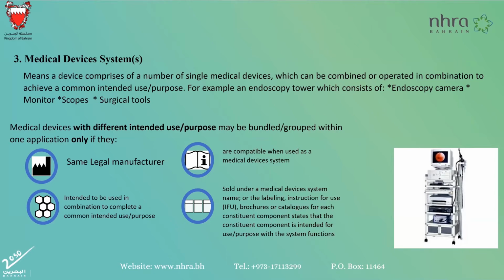A point worth mentioning here is that since they are different medical devices with different intended use, they may contain devices with different risk classifications. So please note that the system risk class will be the highest risk class of the components. So if there are components of class 1, 2, and 3 in the same system, then the system would be regarded as class 3 medical device system.